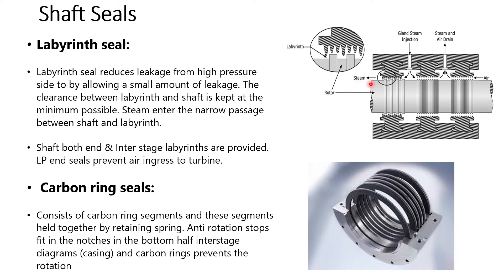Shaft seals are provided on both ends of the shaft as well as between each and every stage. The labyrinth seal reduces leakage from the high pressure side and allows only a very small leakage. In a labyrinth seal there are projection sections both on the casing housing of the turbine and on the rotor. On the high pressure side it prevents steam from going out of the casing, whereas on the low pressure side in a condensing turbine it does not allow air to enter the turbine.